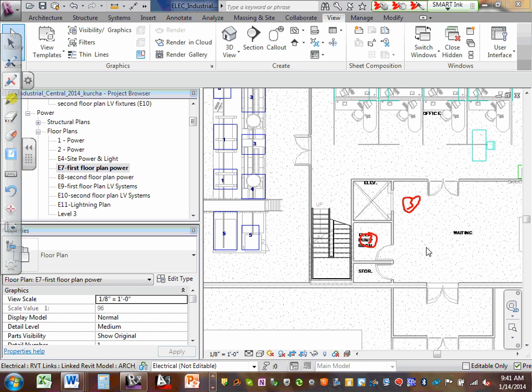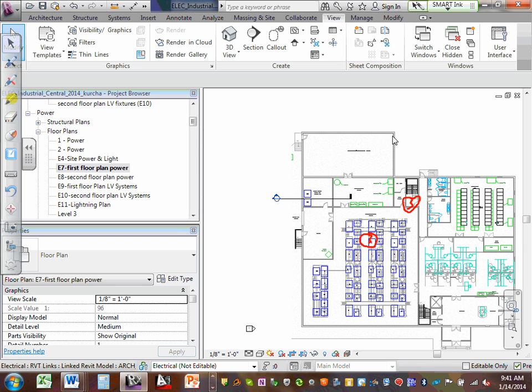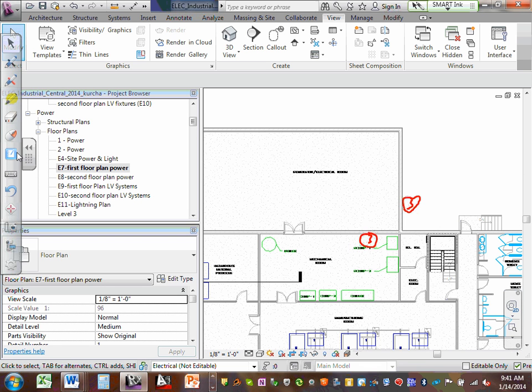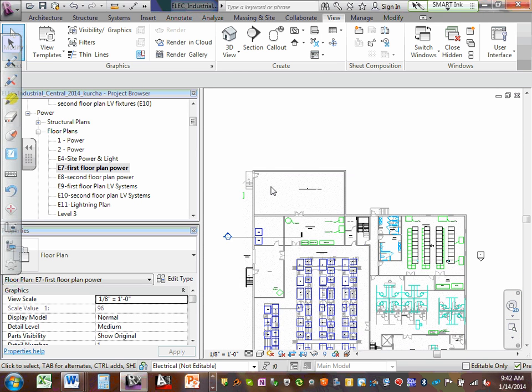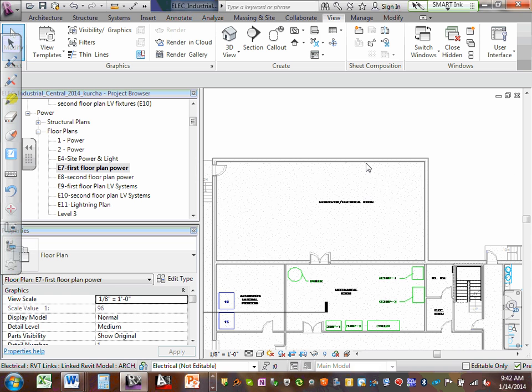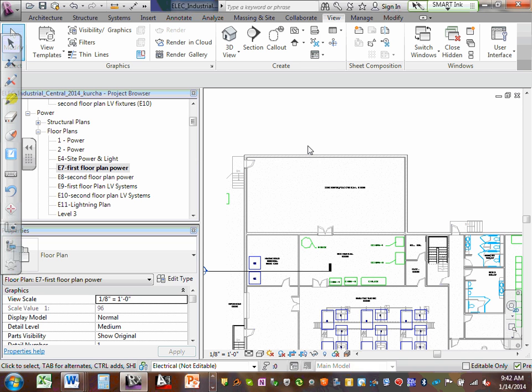What else do we have to do in this building from a fire alarm perspective, even though a fire alarm system is not required? We have to monitor the sprinkler system. Right? The sprinkler code requires that any sprinkler system that has 100 heads or more must be monitored off-site by a UL-listed central station, which in turn calls the fire department. So, in your design criteria, it talks about connection to fire protection system devices as follows: 3 tamper switches and 3 flow switches. It also talks about connection to a fire protection horn strobe located above the Siamese connection on the exterior of the building adjacent to mechanical 116.